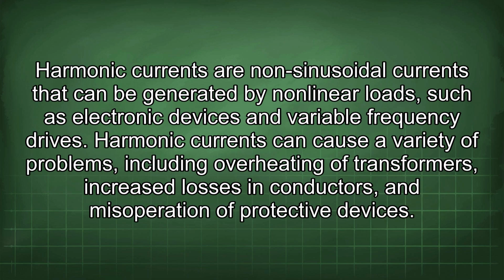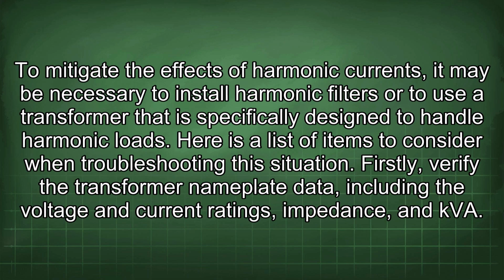system. Harmonic currents are non-sinusoidal currents that can be generated by nonlinear loads such as electronic devices and variable frequency drives. Harmonic currents can cause a variety of problems, including overheating of transformers, increased losses in conductors, and misoperation of protective devices. To mitigate the effects of harmonic currents, it may be necessary to install harmonic filters or to use a transformer that is specifically designed to handle harmonic loads. Here's a list of items to consider when troubleshooting the situation.